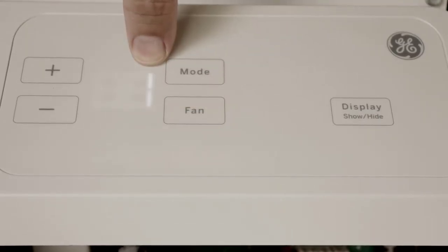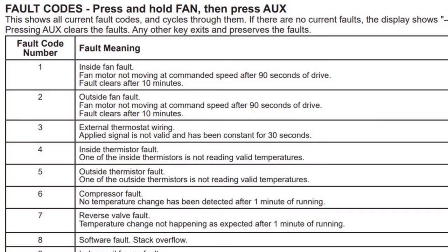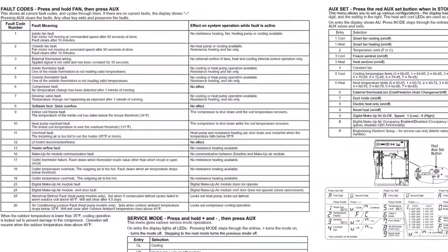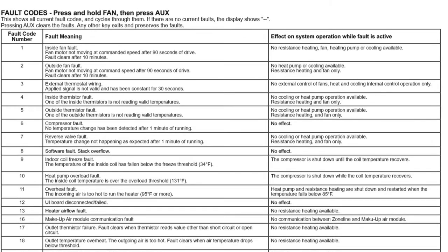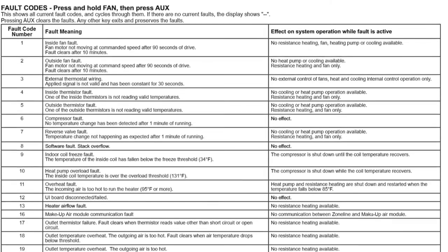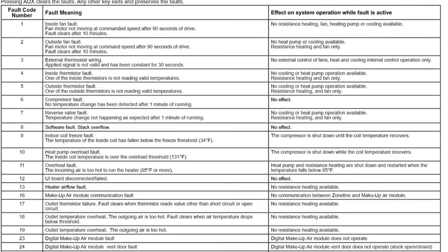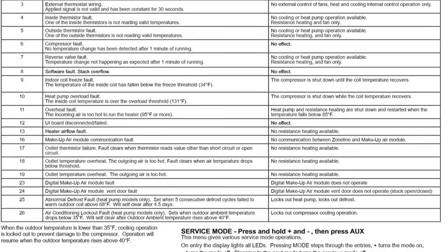One, as shown here, indicates there is an inside fan fault — meaning the inside fan is commanded to run, but there is not an indication that the fan is moving. Refer to the mini-manual that came with your Zoneline PTAC for a complete list of faults and the effects each fault will have on the PTAC operation.